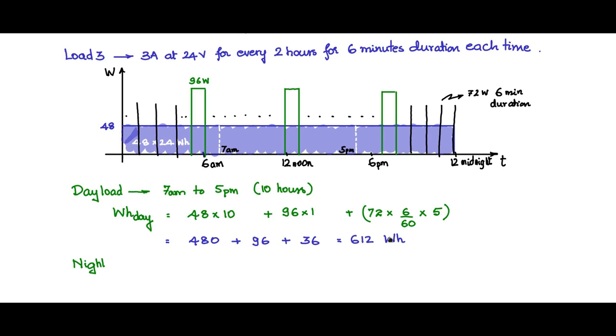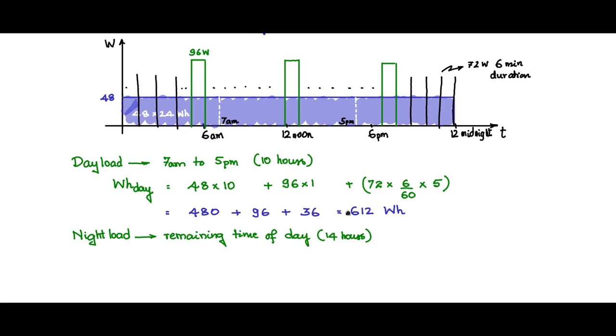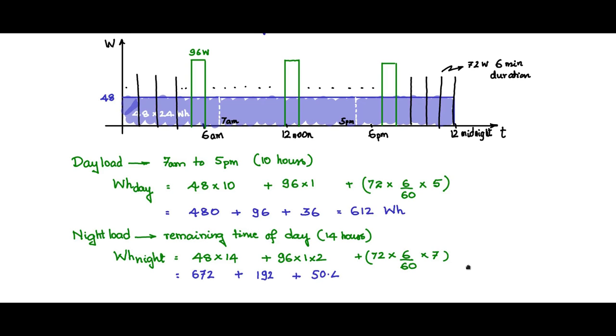The night load covers the remaining 14 hours (24 − 10). Watt-hours night = 48W × 14h + 96W × 2h (two water pump runs outside daytime) + 72W × (6/60)h × 7 (the remaining seven spikes of load 3) = 672 + 192 + 50.4 = 914.4 watt-hours of night load. Together, day and night loads cover the total watt-hours for the entire day.